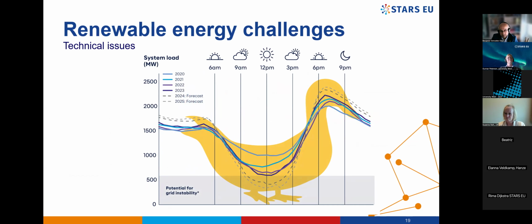The system must accomplish the total demand that we have, but due to this installation, people perhaps do not need as much energy at midday. Therefore, the system must reduce the energy provided by the system operator and the other conventional producers. What happens is that we reduce this technical minimum, and we can enter an unstable condition that can collapse the system, because we don't have enough inertia and enough spinning reserve to accomplish the demand and all the issues we have.